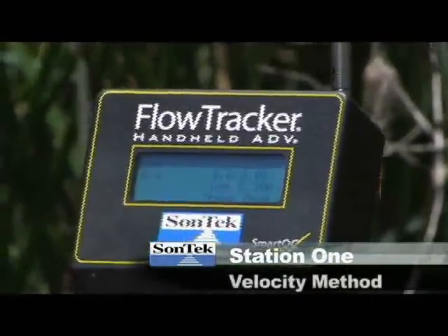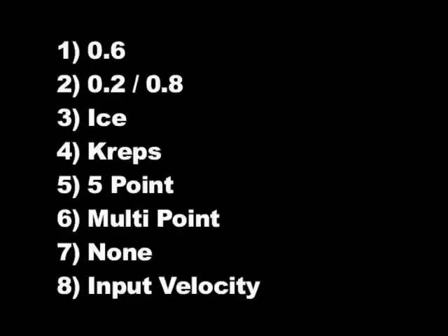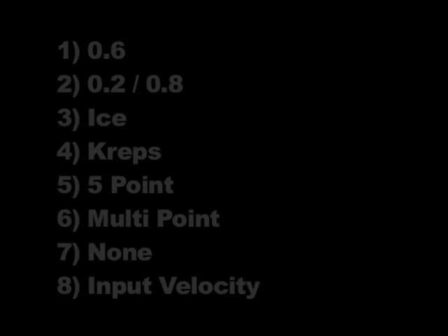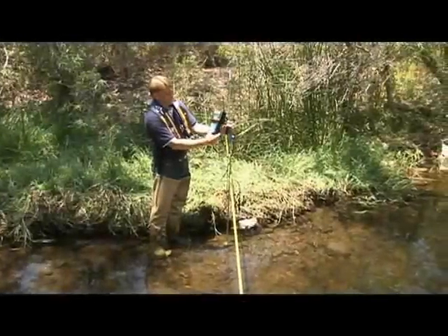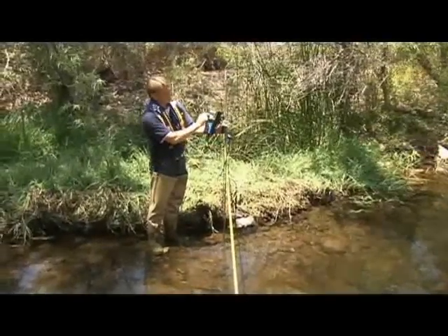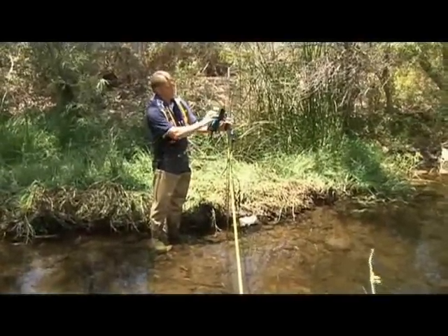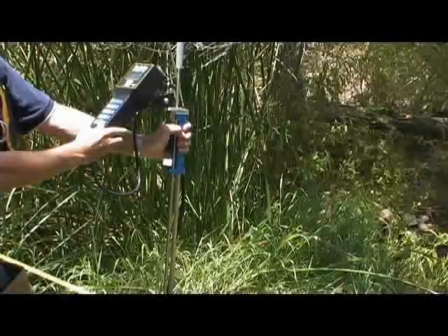Now it says press measure to begin, but I have to make sure that I'm using the correct velocity method to determine mean velocity. There are many methods used to determine the mean velocity. In this case, we're going to use the 6/10 because we're in very shallow water. On the set method, you can see a plus sign, and I just toggle this until it says 0.6. Okay, I've set it at the 6/10 depth.